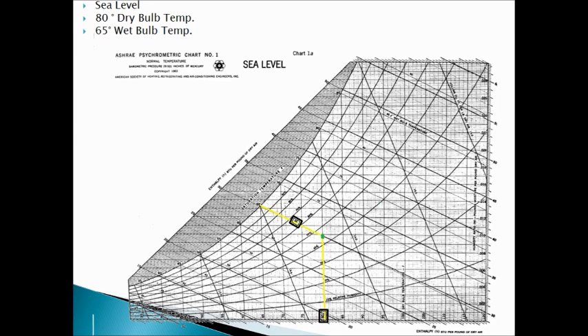Now we can begin reading the other fluid properties. The next property is humidity ratio. To find this property, I'll draw a red line horizontally starting at the state point. Now the value of the humidity ratio can be read. The box shows where this value can be found and it reads 0.010 pound mass of water per pound mass of air.